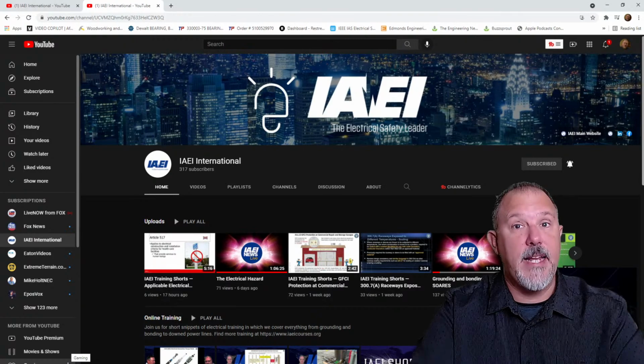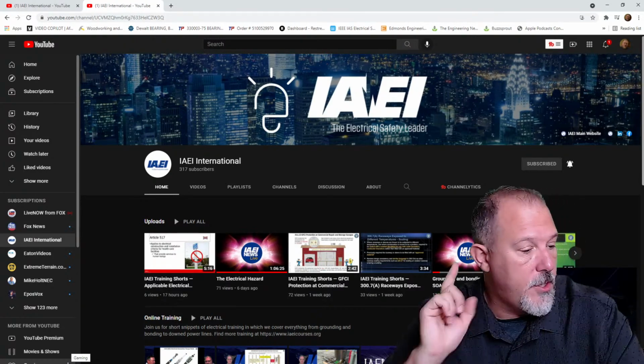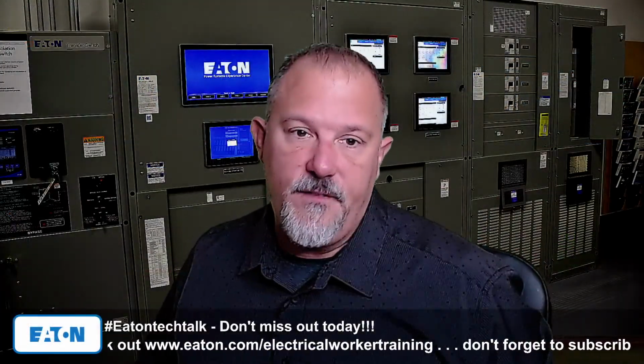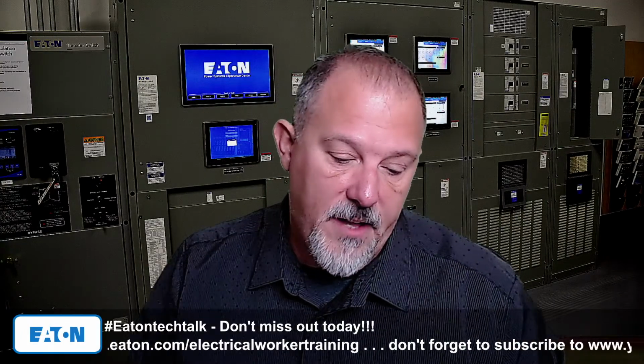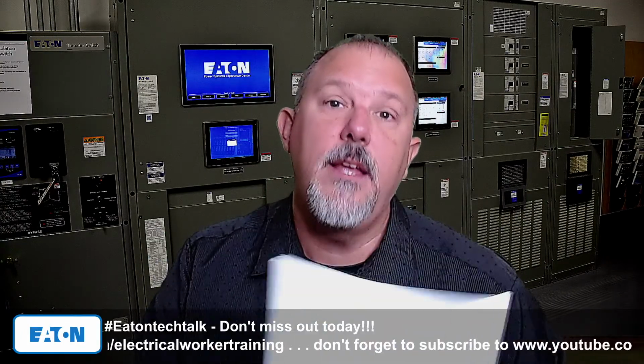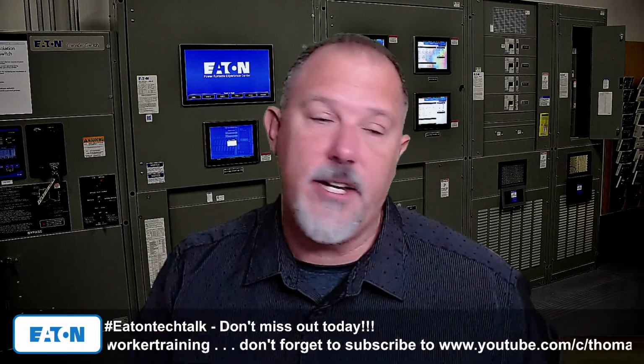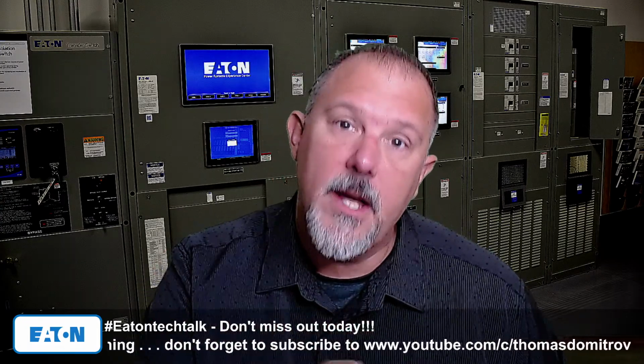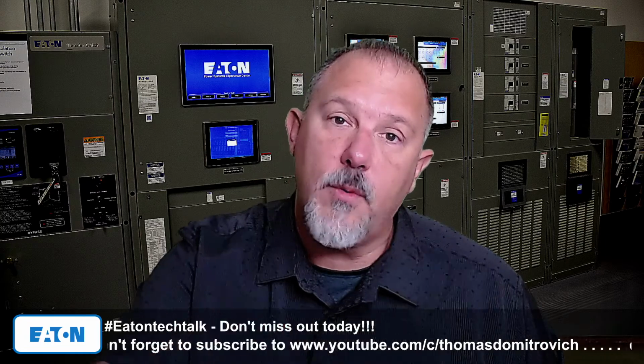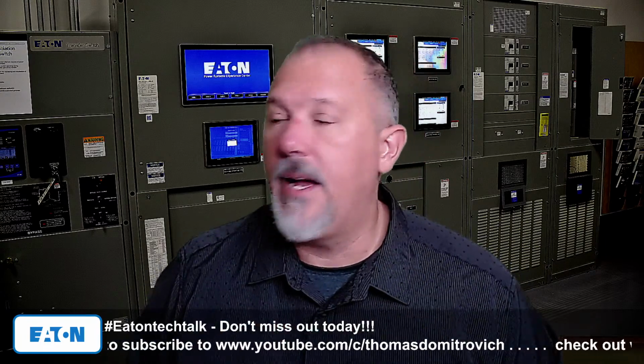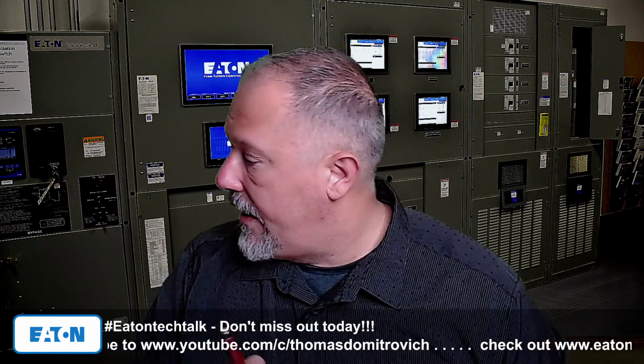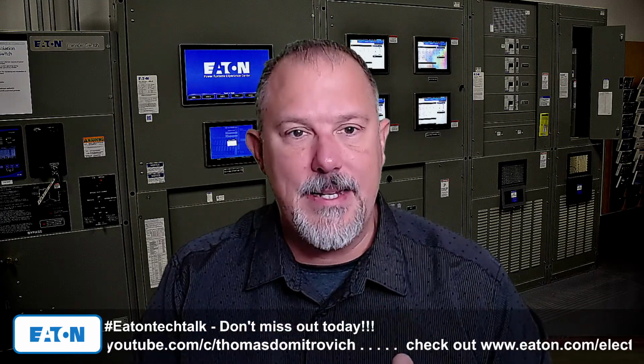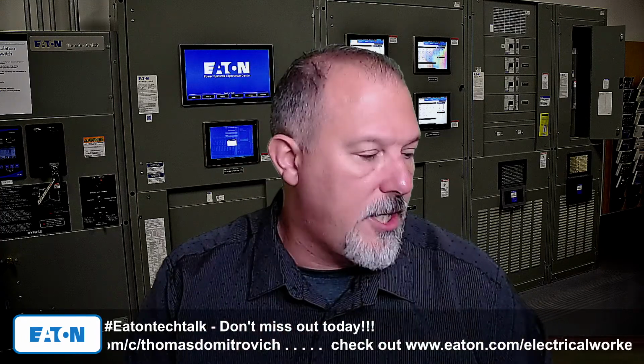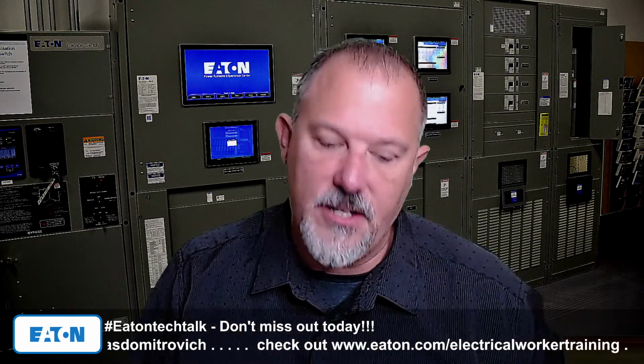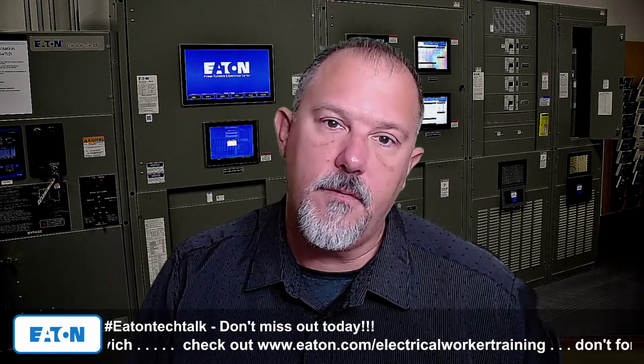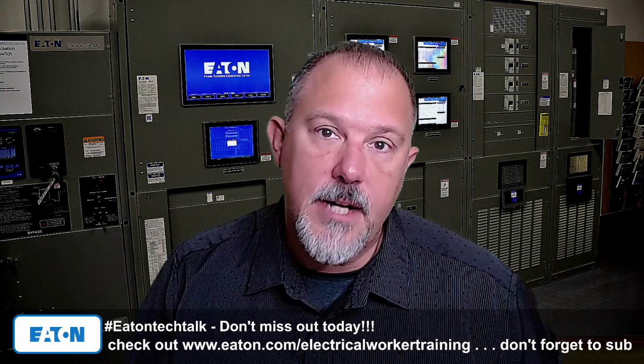When I go live today, I'll be streaming on all three of those. Today's session is focused on the 112.5 kVA transformer—we'll talk about safety, incident energy on the secondary of that transformer, and maybe a little about the 2023 code changes that will impact those applications. That's the plan for today. I'm looking forward to some great discussions at noon and at 5 o'clock p.m. Eastern, so tune in for both on a great Tech Tuesday.